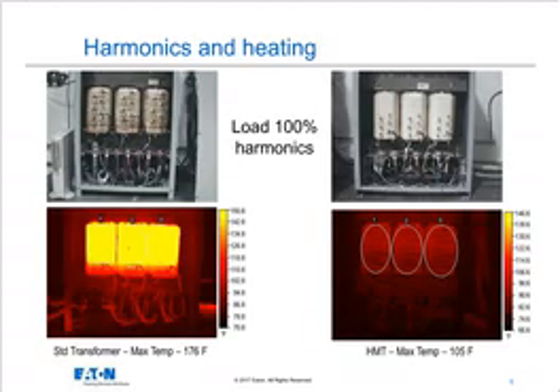Here's an example of 2 transformers. One is a standard transformer on the left, and the other one a harmonic mitigating transformer on the right. The one on the left, you can see with the infrared scan, runs extremely hot. And you can see it's all throughout the windings, not just in one point on the windings. So as an example, at a grade school or a high school, somebody donates 200, 300 computers to the school. They put all those computers in the computer lab, and in the electrical closet, the transformer, a standard transformer, wasn't designed for this heat, starts to burn up, starts to heat up. That transformer will only live about 3 to 5 years, and then all the insulation will start to crack, and then it'll break down and electrically fail.